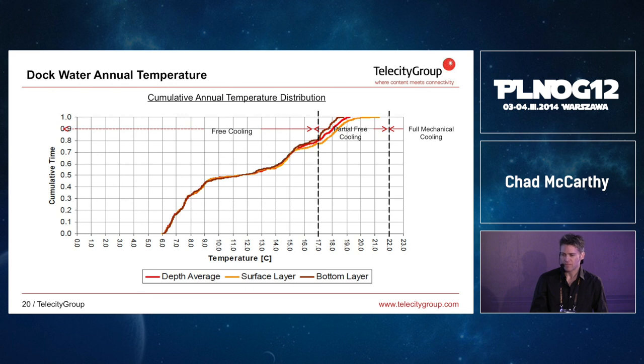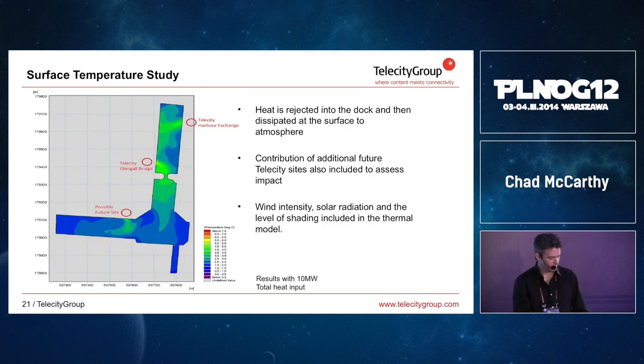We need to focus on the average depth, which is the red trace in the diagram. So this is a CFD study, and this is where we started to look at what would happen to the body of water after we start contributing heat energy into it. So it looks like there's a fairly significant effect, because you can see some bright colors there. The green color indicates around a 5 degrees delta in temperature. But this is at the surface of the dock. So the average temperature, and the temperature underneath the water, is lower.